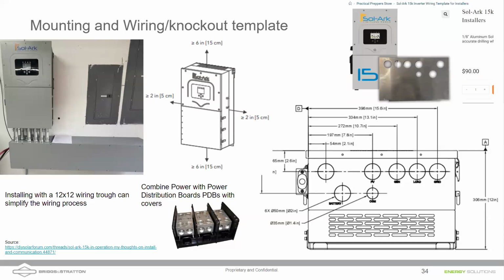And I think I'll handle that one. A lot of these load shedding devices are pretty intelligent. They're using certain triggers, whether it's exceeding the amount of power being drawn upon the inverter, but they can also trigger load shedding devices based on the remaining capacity in a battery as well. So there's lots of ways to do these load shedding devices that are becoming more intelligent all the time, and that could be a training in and of itself, Nathan, that we could do coming up. So stay tuned for something like that if that's something that interests you.